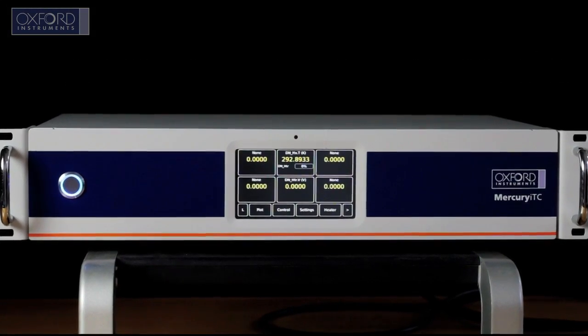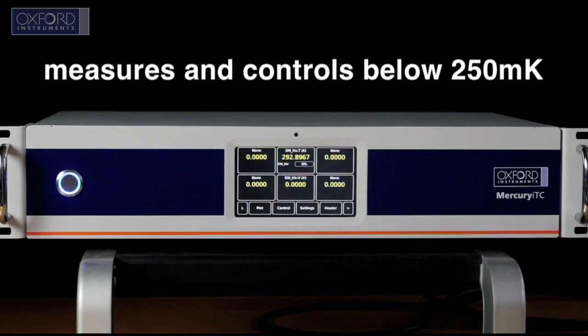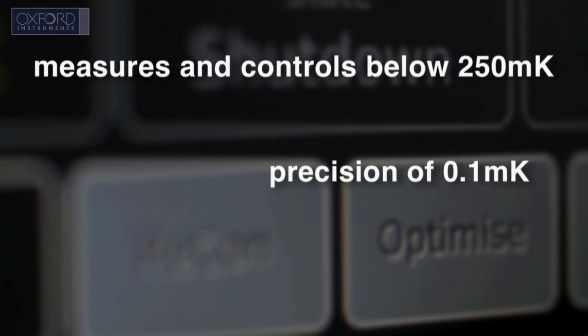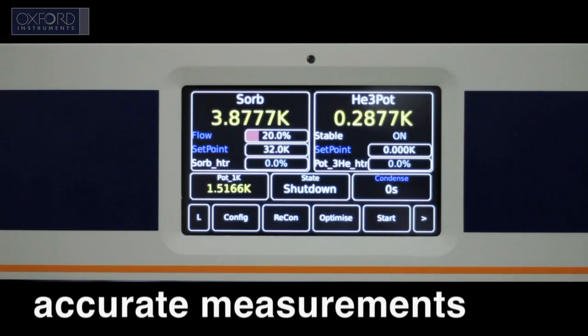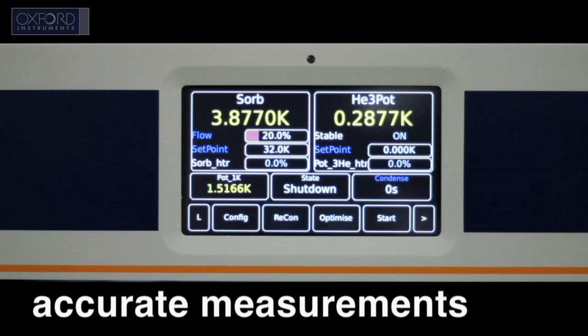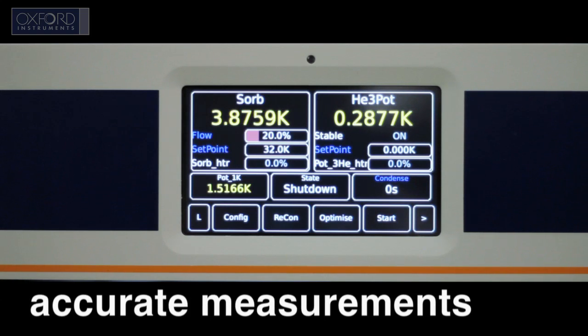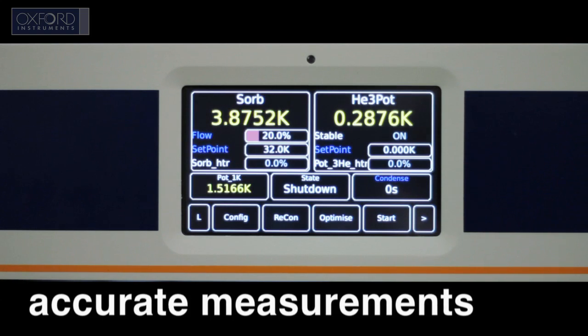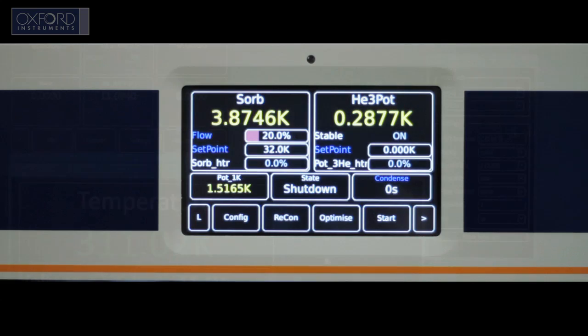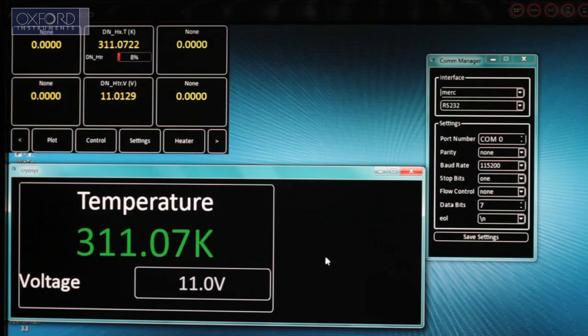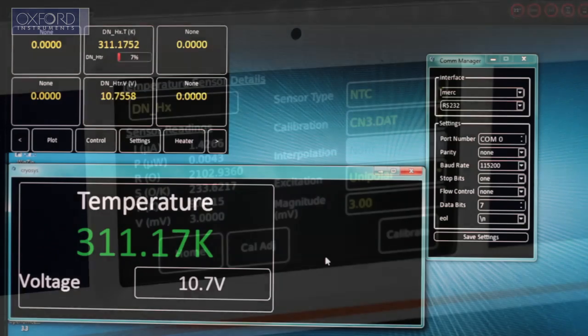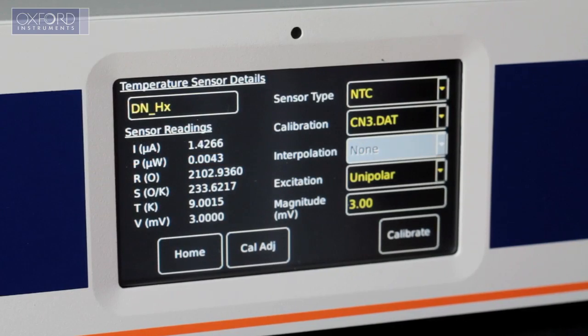The Mercury ITC can measure and control temperatures to below 250 mK with a precision of 0.1 mK. It uses a true constant voltage source for sensor excitation, preventing self-heating and allowing for high-quality measurements at the lowest temperature.